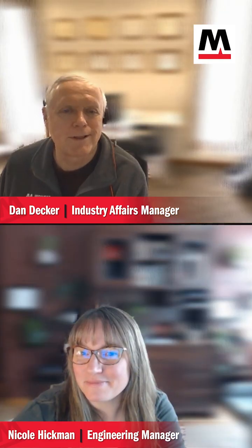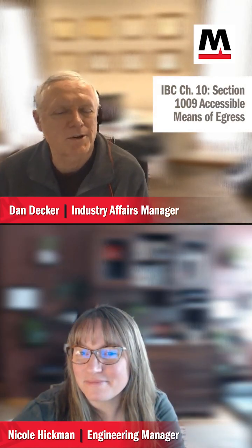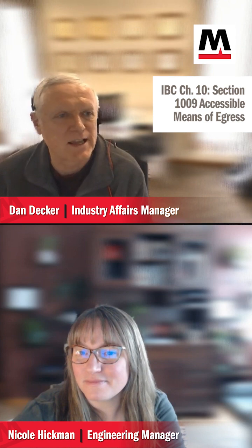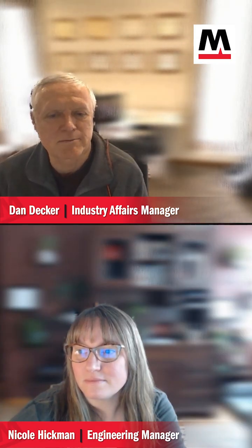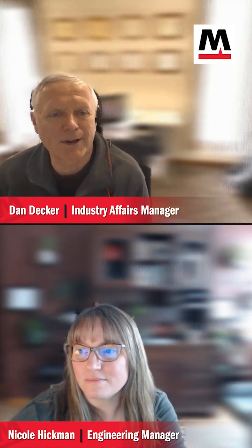Since we're in the electronics business, section 1009 of chapter 10 covers accessible means of egress. That includes areas of refuge. Areas of refuge need a two-way communication system to a central control point like a fire command center. Sometimes they have to call off site. So those are systems that our industry installs. It's good to know when they're required because sometimes somebody might miss it. It's better to catch it before we submit plans rather than be an urgent matter when they're trying to get occupancy. We do access control too.